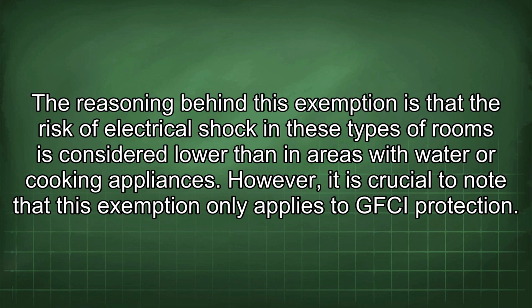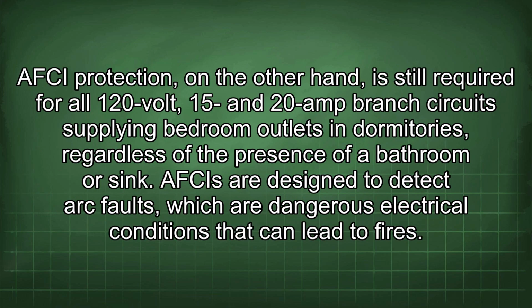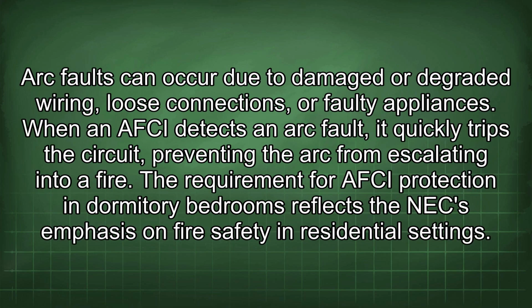However, it is crucial to note that this exemption only applies to GFCI protection. AFCI protection, on the other hand, is still required for all 120 volt, 15 and 20 amp branch circuits supplying bedroom outlets in dormitories, regardless of the presence of a bathroom or sink. AFCIs are designed to detect arc faults, which are dangerous electrical conditions that can lead to fires. Arc faults can occur due to damaged or degraded wiring, loose connections, or faulty appliances. When an AFCI detects an arc fault, it quickly trips the circuit, preventing the arc from escalating into a fire.